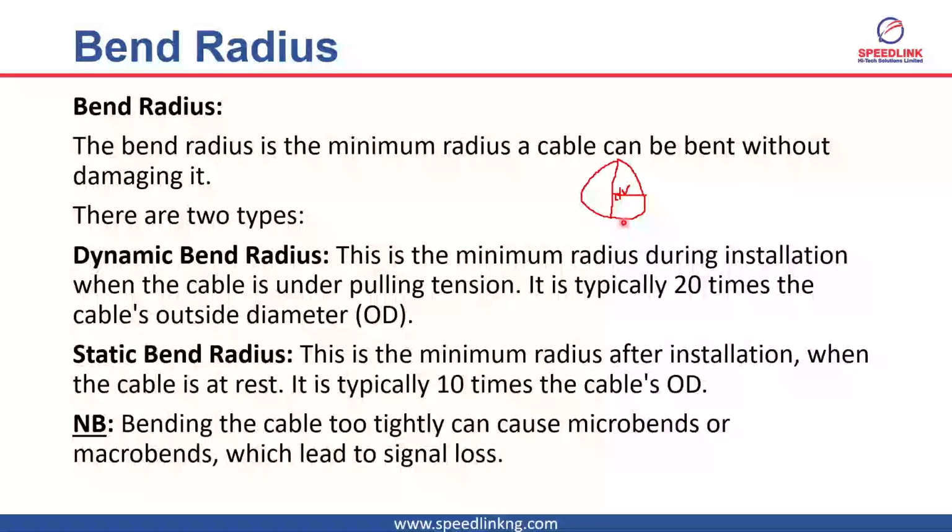Yes. Now, what's the formula there? Remember, that would be a static bend now, because we're not pulling the cable at that point in time. The cable is resting, right? So that's a static bend. So that static bend is what? 10 times the cable's outer diameter. Are we getting that? Yes.